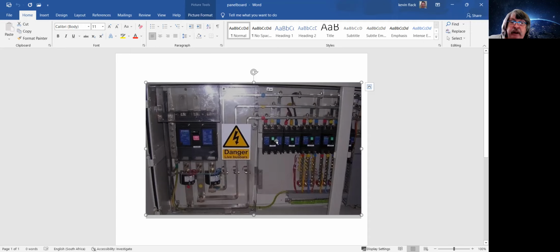What we could have on here as another area of concern was if this was a 525 volt panel and we had a control voltage here, and we dropped droppers down from the busbars to the control transformer, and we had 10 amps required on that control transformer. The cables that are connected from the busbar to the transformer in this zone have to be protected, one, from the kA, and two, from the mechanical stresses to that cable. So there's no way you could drop a piece of cable down here to a fuse set down the bottom and then go into the transformer.